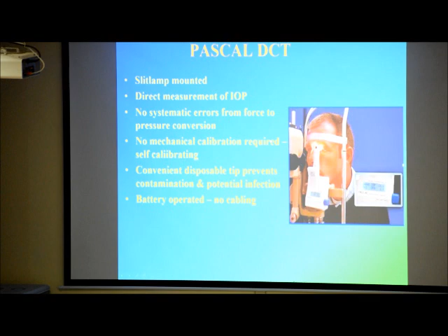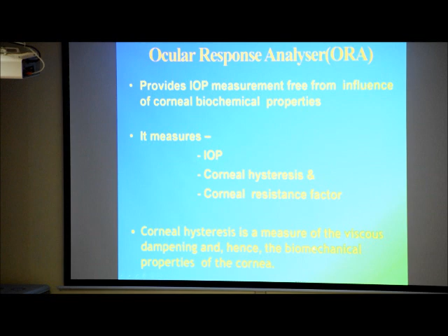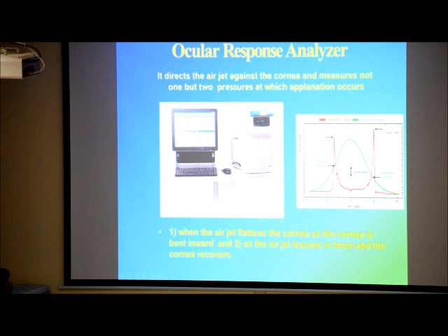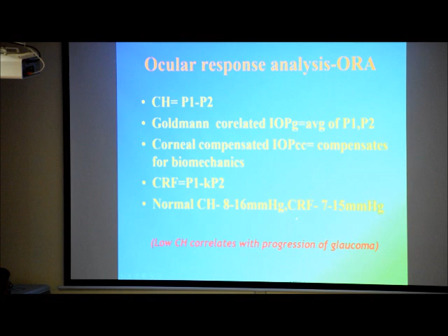The ORA, ocular response analyzer, provides intraocular pressure measurement free from the influence of corneal biomechanical properties. It measures three things: intraocular pressure, corneal hysteresis, and corneal resistance factor. Corneal hysteresis is the measurement of viscous damping and hence the biomechanical properties of the cornea. It directs an air jet against the cornea and measures not one but two pressures when applanation occurs. The first pressure, P1, is when it applanates the cornea, and the second, P2, is when the cornea recovers. Intraocular pressure is the average of P1 and P2, and corneal hysteresis is P1 minus P2. Low corneal hysteresis correlates with the progression of glaucoma.